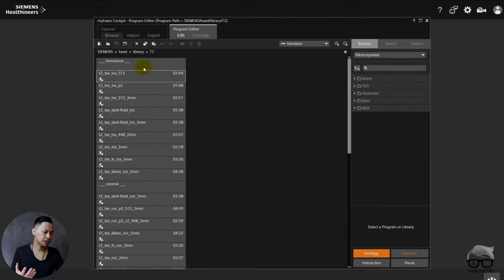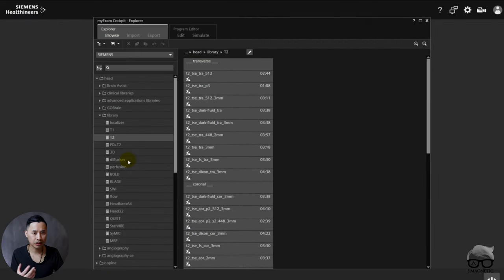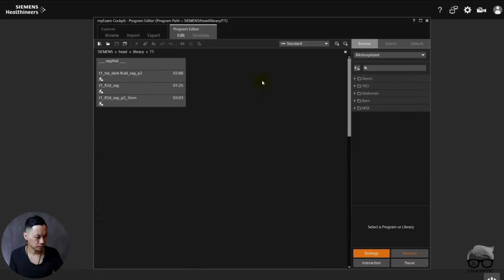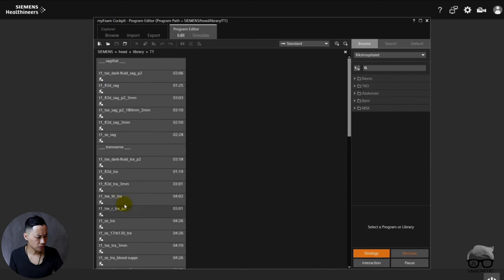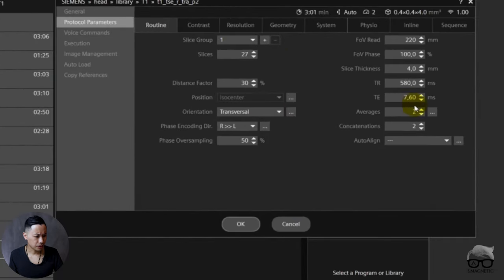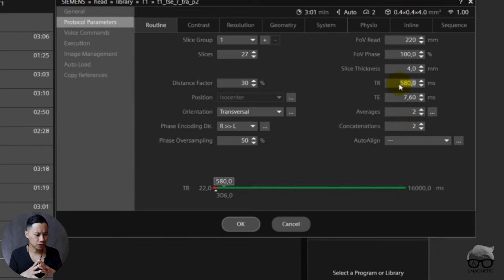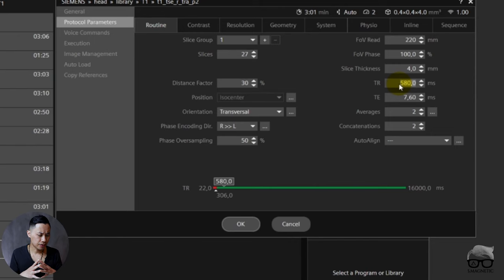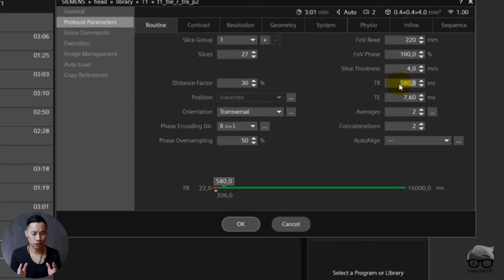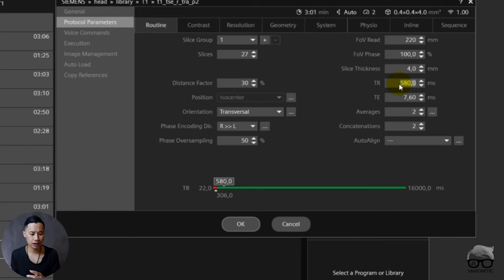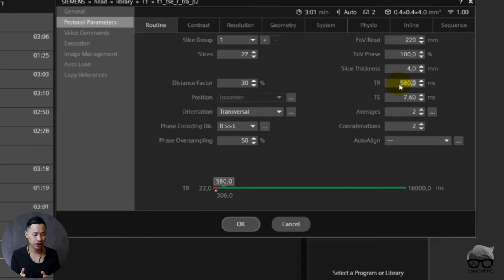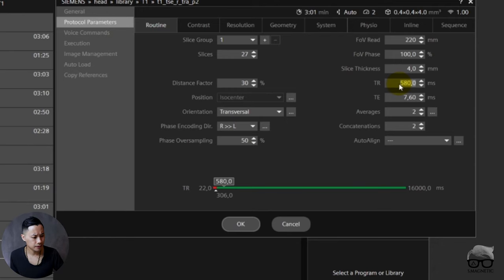Okay, so let's check another sequence. Let's check out T1 2D spin echo. So we go to edit mode. Let's find a T1 2D spin echo right there. You can see with two concats we now have a TR of 580, but I can lower it to 306, but that will be too low within that T1 contrast. You also have to remember what field strength you have. T1-weighted, T2, STIR, PD, they all have different ranges, so we remember that.